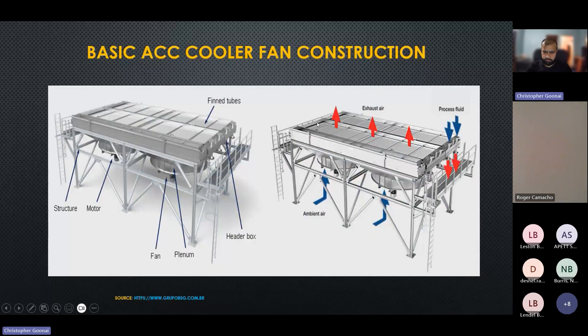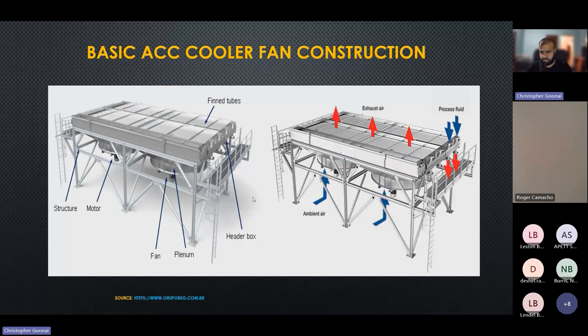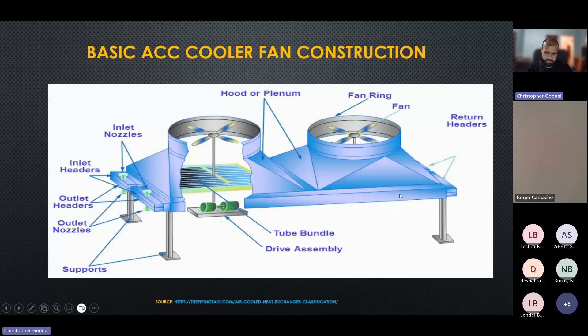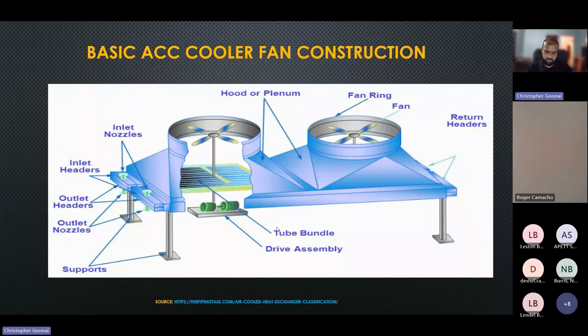Here is the structural makeup of the cooling fan itself. You have the fan surrounded by the shroud or fan ring. You have the plenum that encapsulates everything — like the shell that holds everything and secures it — as well as the structure itself and the header for the cooler, where processed fluid enters, whether it's hot processed fluid or gas. This next construction shows an induced draft type with header and nozzle inlets and outlets. This design illustrates a right-angle drive — it could be a right-angle gearbox, a direct drive, or a parallel gearbox.